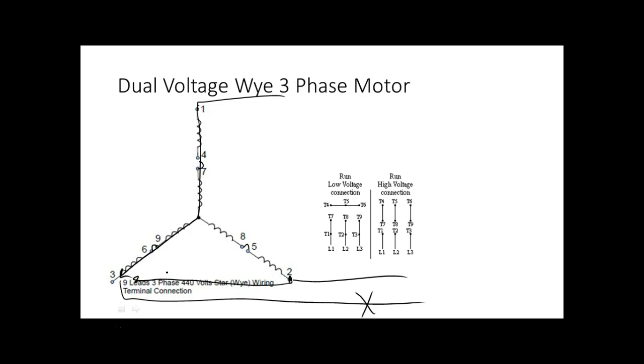So with 3-phase motors running, it's pretty hard to find an open lead. What most people do is depend on clamp-on ammeters. They clamp across the 3 phases, and one of the phases will be conducting zero current. But the motor's going to start humming because the other 2 phases try to make up the work.